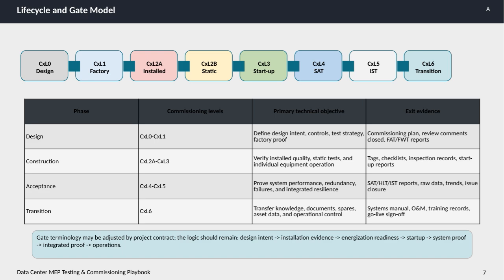Moving on to the construction phase, which covers CxL2A to CxL3, the focus shifts to verifying quality of installed systems, performing static tests, and ensuring individual equipment operations are correct. The documentation necessary to exit this phase includes tags, checklists, inspection records, and startup reports. Next is the acceptance phase, encompassing CxL4 and CxL5. Here, the emphasis is on proving system performance, ensuring redundancy, handling failure scenarios, and validating integrated resilience. Key evidence for this stage includes site acceptance tests, heat load tests, integrated system test reports, raw data, trending information, and resolution of any issues. Finally, the transition phase at CxL6 involves transferring all relevant knowledge, documentation, spare parts, asset data, and operational control to the client or facility management team.